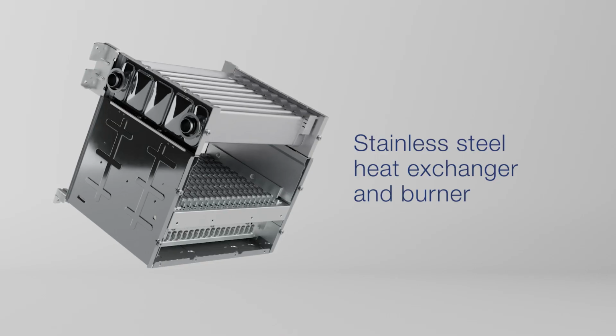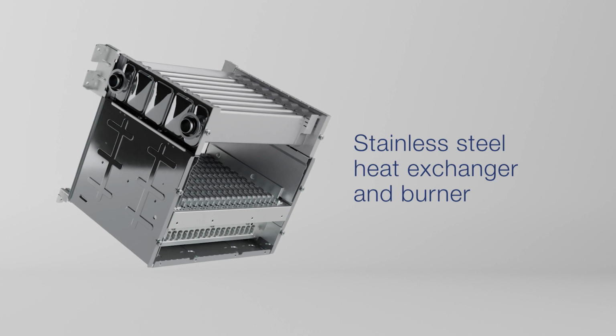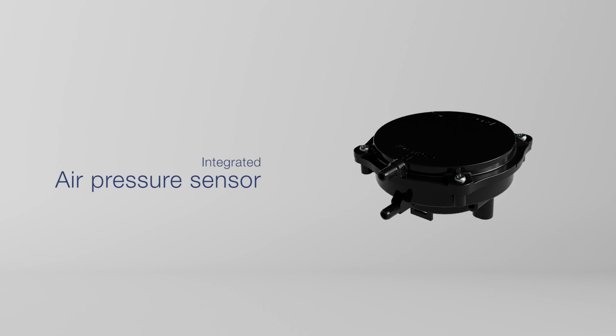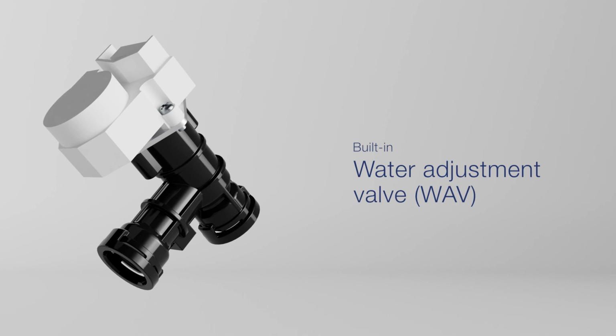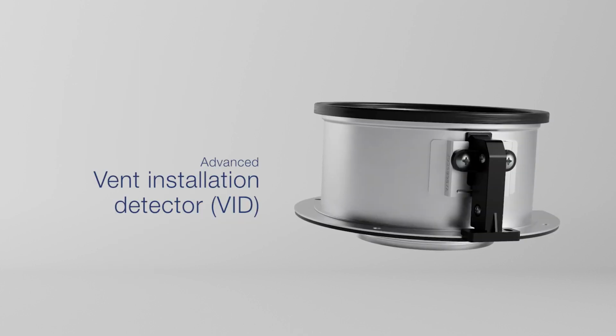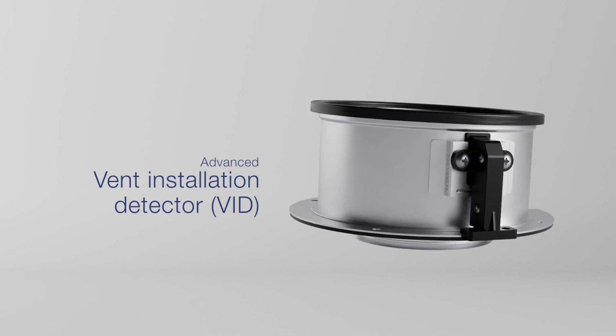Navien still is the only non-condensing water heater in the industry with a stainless steel heat exchanger and burner, which delivers efficiency, durability, and longevity. The integrated air pressure sensor ensures proper combustion and automatically compensates for variable vent lengths or changing pressure conditions. Each unit also has a built-in water adjustment valve, which means that the outlet water temperature remains constant no matter the demand. Safety remains a priority for Navien, and the NHW is no different, with features such as the advanced vent installation detector, which prevents the operation of the unit if the exhaust pipe is not properly connected.